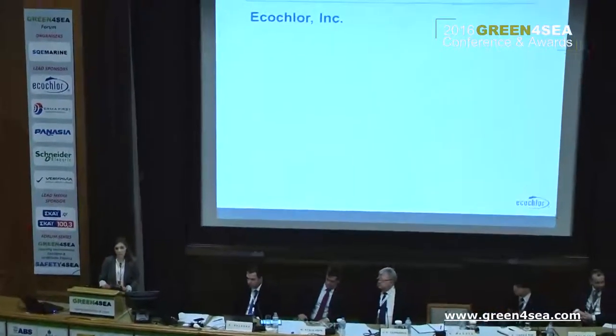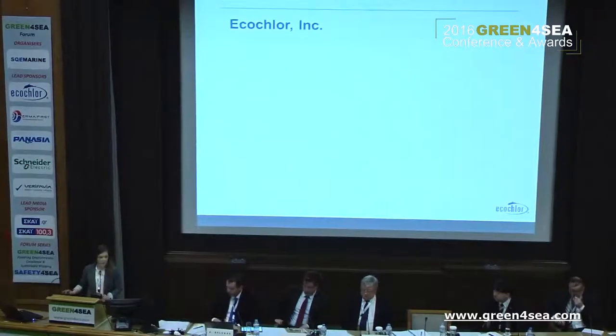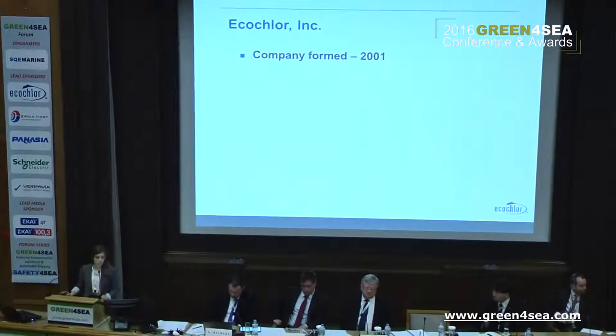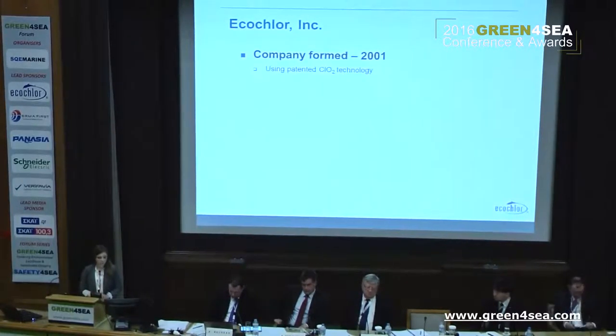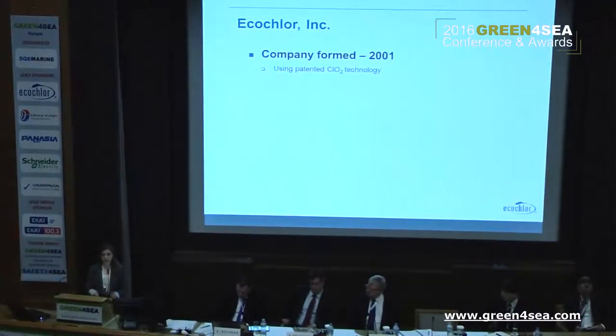I'll give a brief background about Ecochlor to familiarize you with our company. Our company was formed in 2001, and we make a ballast water treatment system that uses patented chlorine dioxide technology. We treat ballast water in two steps: first filtration, and then injection of chlorine dioxide into the ballast line. We use chlorine dioxide because it's highly effective and very effective regardless of changes in water quality, so we don't need to change how our system operates based on turbidity, salinity, or temperature changes, nor do we change the dose.